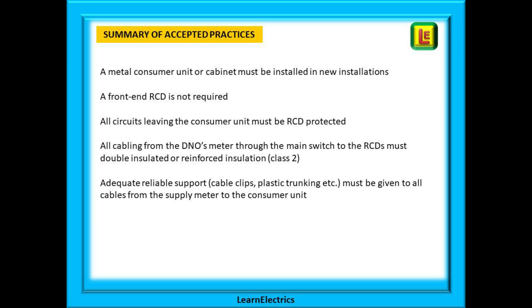If we summarize what we must do when installing a TT consumer unit: a metal consumer unit or cabinet must be installed in new domestic installations. A front-end RCD is not required. All circuits leaving the consumer unit must be RCD protected, and all cabling from the DNO's meter through to the main switch and onto the RCDs must be double insulated or reinforced insulation, making it Class II. Adequate and reliable support such as cable clips and plastic trunking must be given to all cables from the supply meter to the consumer unit, as this will be the weak point in the system.